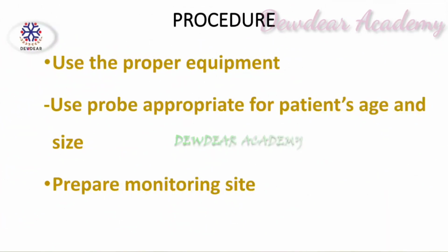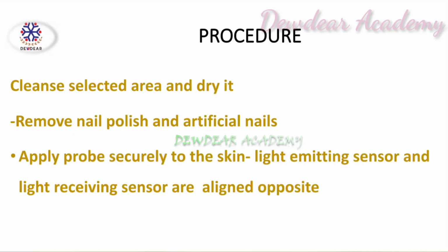Then use the proper equipment. Use probe appropriate for the patient's age and size, and prepare the monitoring site. So cleanse the selected area and dry it, and remove the nail polish and artificial nails, and then we can apply the probe securely to the skin. Light emitting sensor and light receiving sensor are aligned opposite.